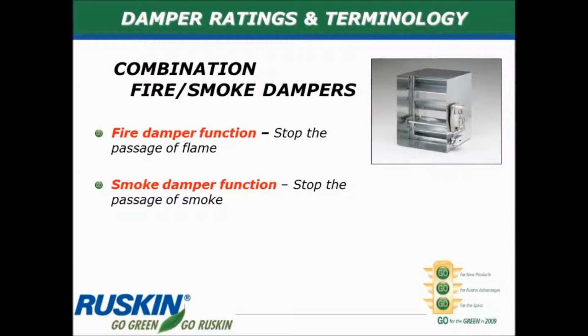Just like a smoke damper, it is motor operated. Those actuator motors for life safety dampers must be power open, fail, spring return, close. So they're always energized, cranking the blades in the open position during normal operation of the building. If there is a fire detected within the building, a signal is sent, it cuts off the power to the actuator motor, and the internal spring cranks the blades closed. Even though the life safety dampers are part of the HVAC system within a building, technically they are not part of the ductwork. They are part of the partition that they are designed to protect.